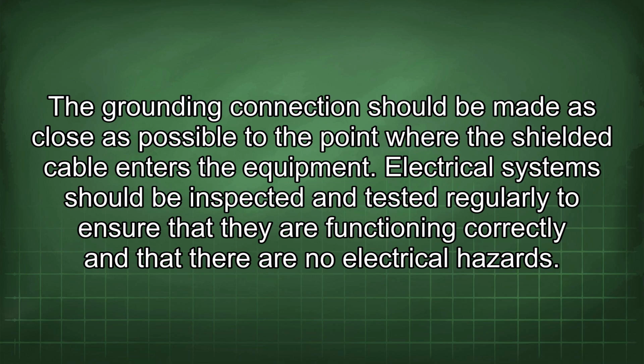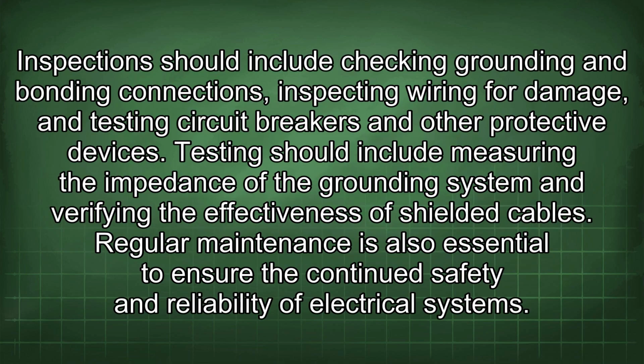Electrical systems should be inspected and tested regularly to ensure that they are functioning correctly and that there are no electrical hazards. Inspections should include checking grounding and bonding connections, inspecting wiring for damage, and testing circuit breakers and other protective devices. Testing should include measuring the impedance of the grounding system and verifying the effectiveness of shielded cables.